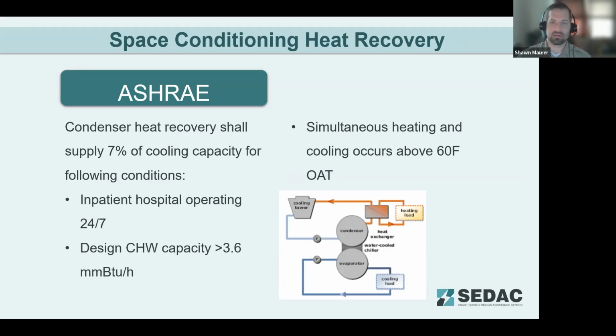Space conditioning heat recovery. ASHRAE includes condenser heat recovery. We're looking at heat recovery chillers here for large systems that have simultaneous heating and cooling needs. So you're looking at providing low-cost heating or low-cost cooling, depending on your perspective and what the core base load is. And so that condenser heat recovery is supposed to supply 7% of your cooling capacity for inpatient hospitals operating 24/7. They typically have a large cooling capacity 24/7 of the year just because of all the equipment and occupancy in those spaces. Design chilled water capacity of 3.6 million BTUs per hour and simultaneous heating and cooling that occurs above 60 degrees Fahrenheit outdoor air temperature. So you're looking at reheat there essentially.